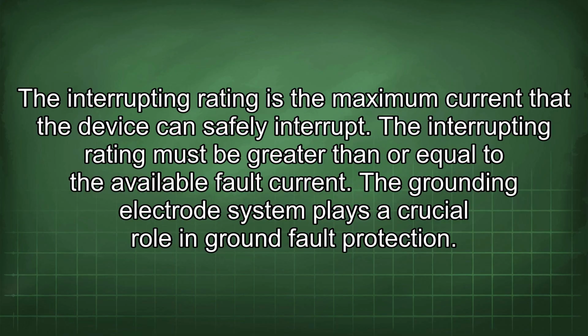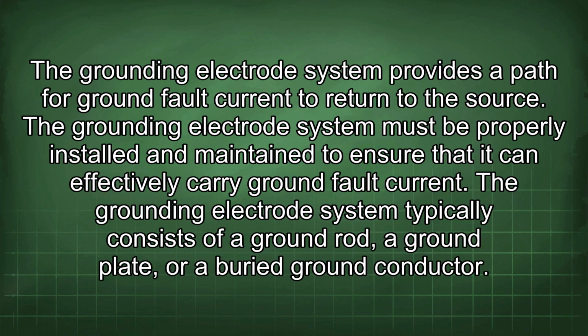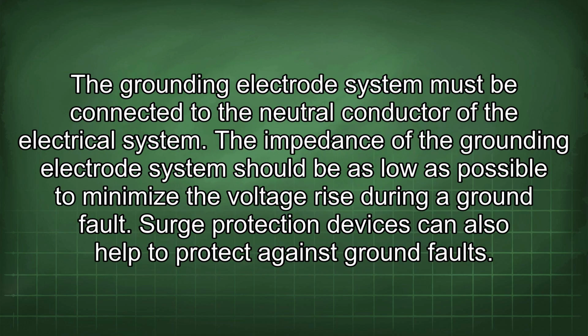The grounding electrode system plays a crucial role in ground fault protection. The grounding electrode system provides a path for ground fault current to return to the source. The grounding electrode system must be properly installed and maintained to ensure that it can effectively carry ground fault current. The grounding electrode system typically consists of a ground rod, a ground plate, or a buried ground conductor. The grounding electrode system must be connected to the neutral conductor of the electrical system.